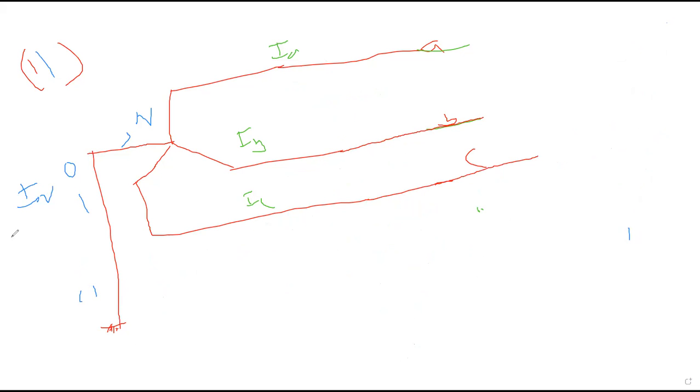This is the phase C. So how do we place? We place 3 CTs, and the connections are made in such a way that if the primary and secondary currents flow in opposite directions, if the primary current flows from left to right, the secondary current will be from right to left, like what we have configured in differential protection. Understood?